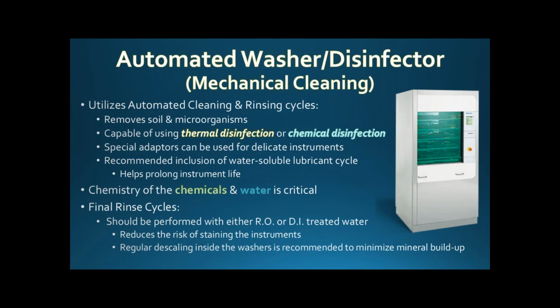You want to look at that whole span of what happens on that side. You also want to make sure your equipment is performing a final rinse with either RO or DI water, because you want to make sure you're taking all that mineral deposit out, and that your instruments are rinsed and you get all that out. One way to know if you have problems with mineralization is to look at the inside of your washer, or ask your team how often they need to descale it. If they have a lot of white residue or are having to do frequent descaling to get rid of that, you might have some challenges with your water. That's something you can ask them about and make sure you're constantly evaluating. Also look at your instruments, because you can typically tell when they're starting to get a little dull if it's due to the water.